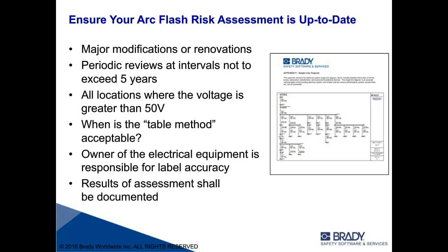And it's really important to understand that if you simply move a piece of equipment from one side of the room to the other, the label that was on the piece of equipment before is no longer accurate. That change in distance alters the calculations, which is going to potentially change the incident energy levels at that piece of equipment. So it's important to understand that very minor changes to your electrical system can impact the incident energy level at your equipment.